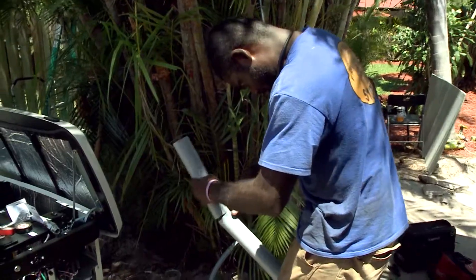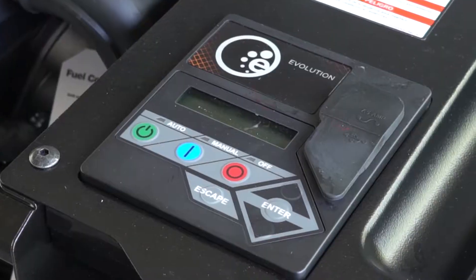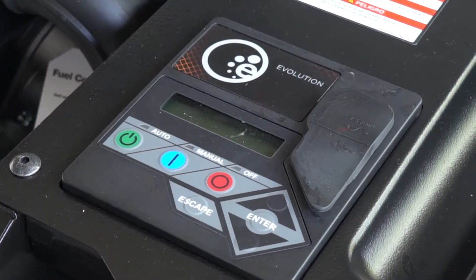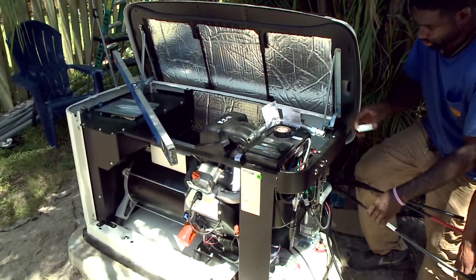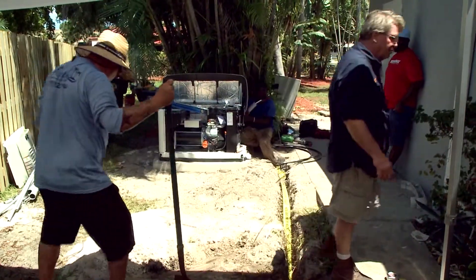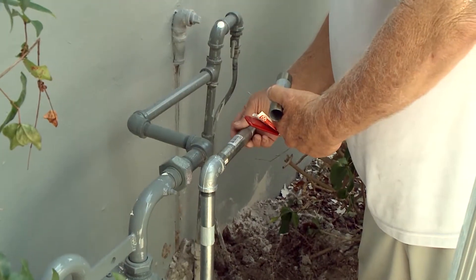Tell me how this works — it's always ready to go, and you can hear the thunderstorms are rolling in, so we need to get this installed pretty quick. How does it work? This is a 22 kilowatt natural gas fired backup power generator. When you lose utility power, this will automatically come on and pick up all the loads in your house. There's logic in the controller that runs a weekly diagnostic cycle to make sure the generator is always ready to go. The generator runs on natural gas, so that's being managed also.